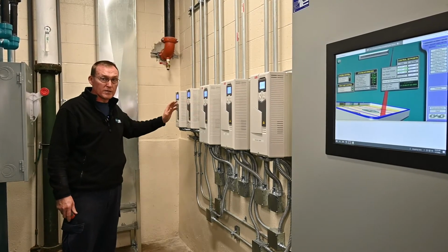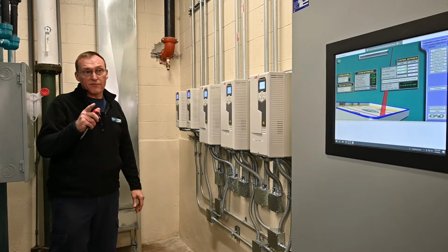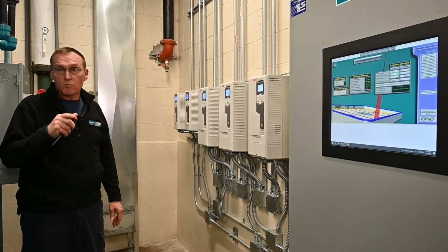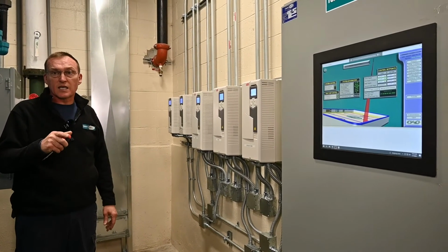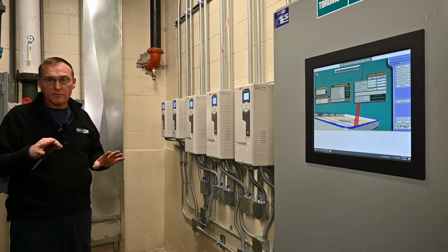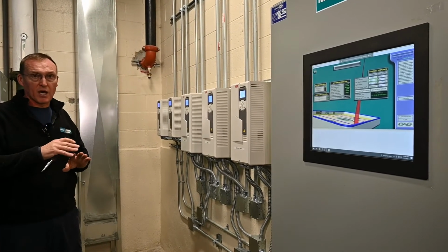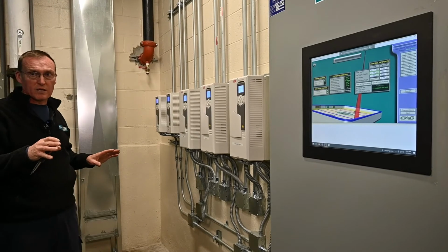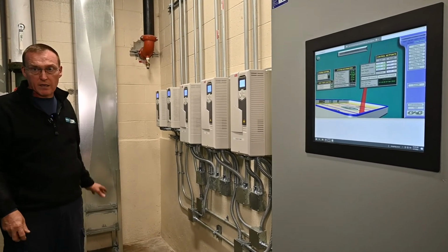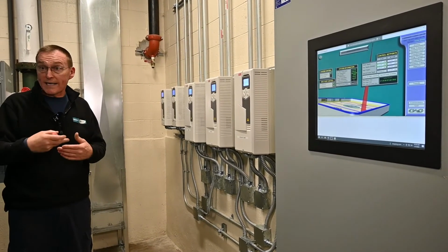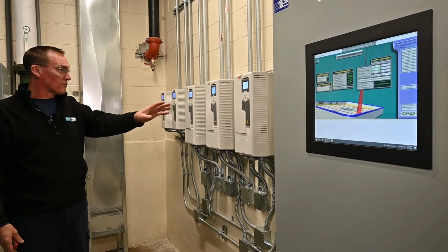If you have a power failure, we have power and phase protection within the panel. The second that it sees any kind of blip, it will shut everything off, control-wise, okay? It'll dump the 120 volts within control power within the plant, and everything will go dead, okay? When the power comes back and it's right, then it'll reboot everything and repower everything.